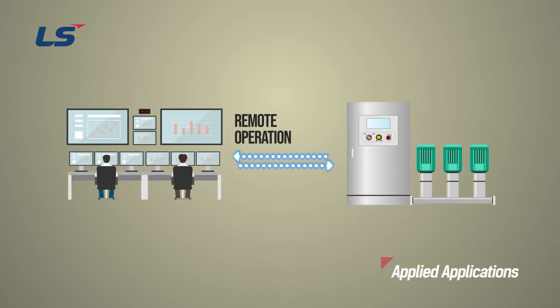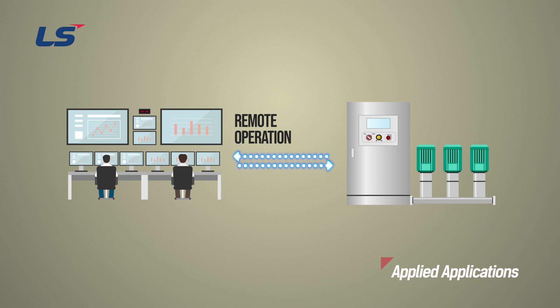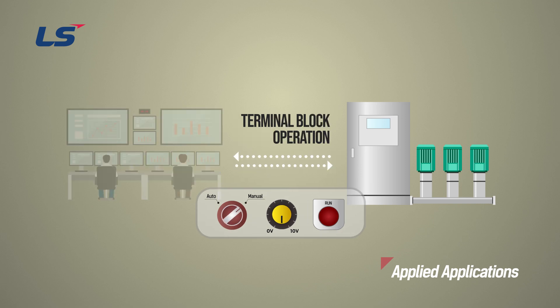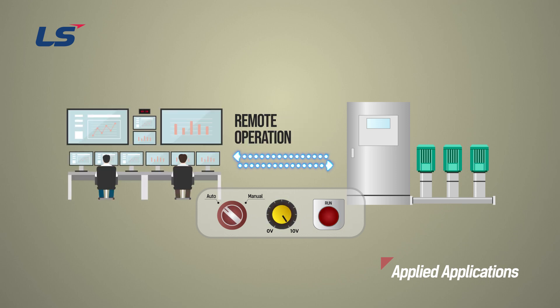This function can be applied when you want to directly operate the inverter in local control. By operating the switch connected to the inverter on the outside of the panel, the remote command is disabled and the inverter can be operated by the use of terminal block or keypad. The original operation method can be resumed by using the remote operation switch on the panel.